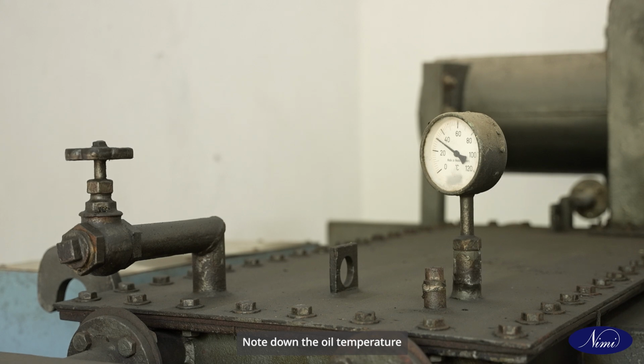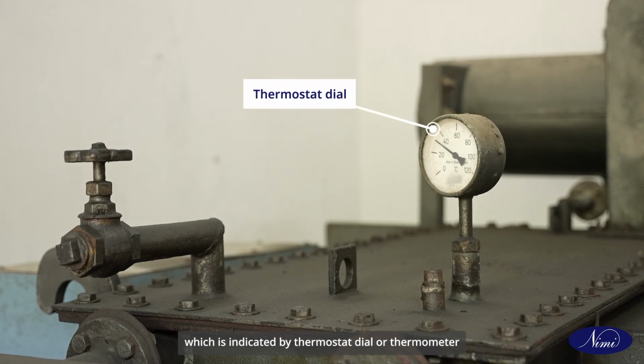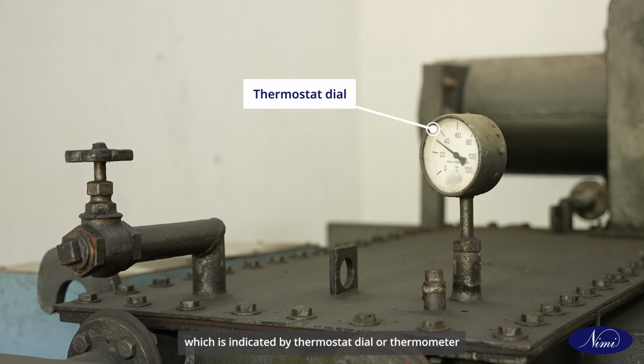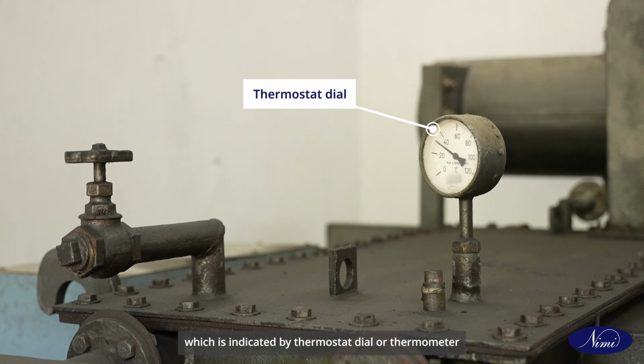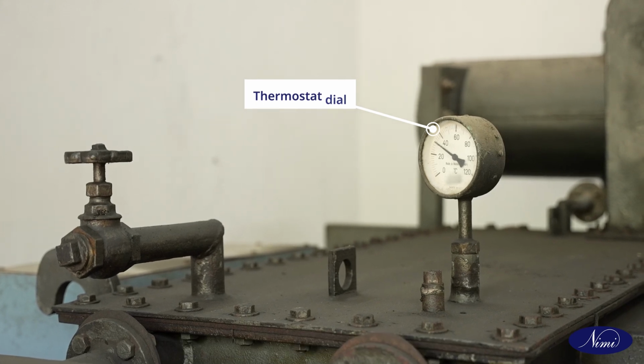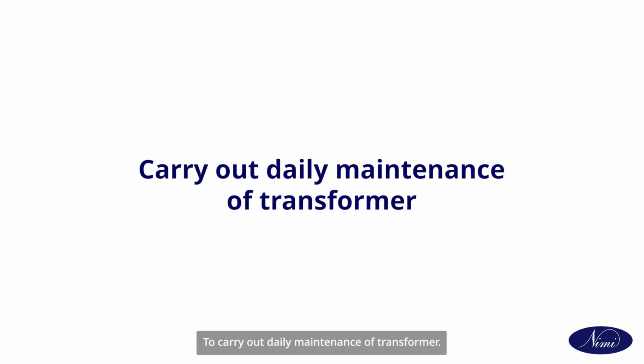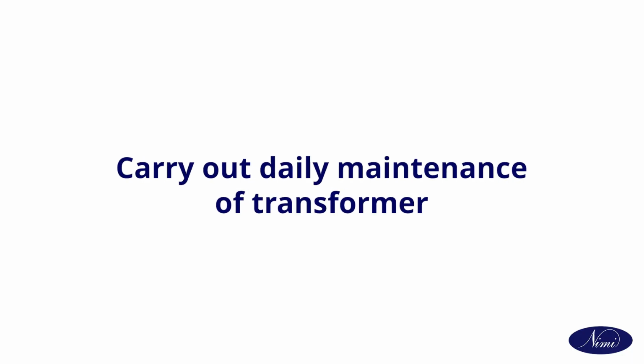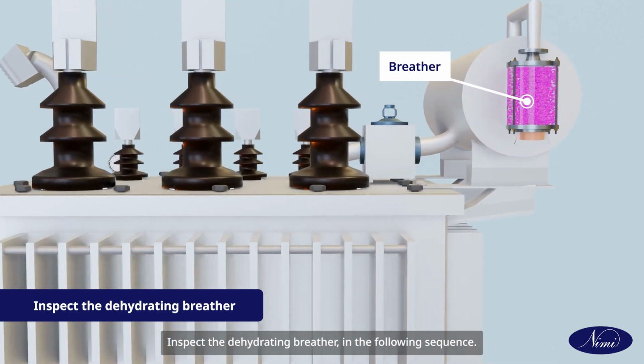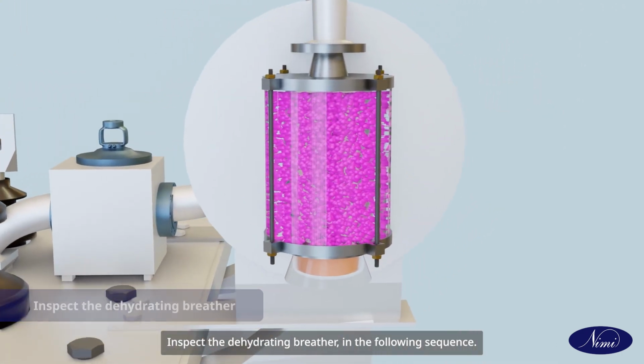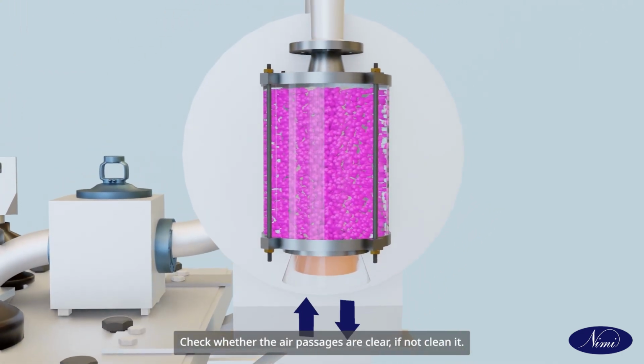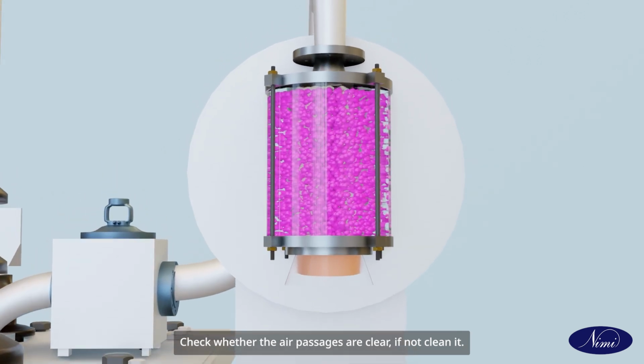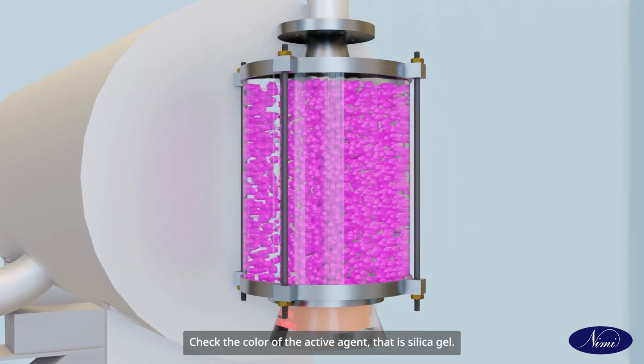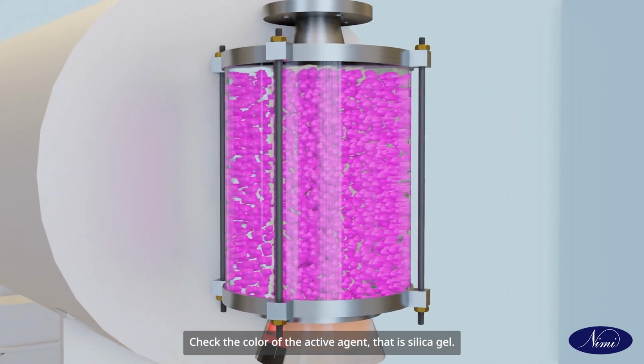Note down the oil temperature, which is indicated by thermostat dial or thermometer. To carry out daily maintenance of the transformer, inspect the dehydrating breather in the following sequence. Check whether the air passages are clear. If not, clean them. Check the color of the active agent, that is silica gel.